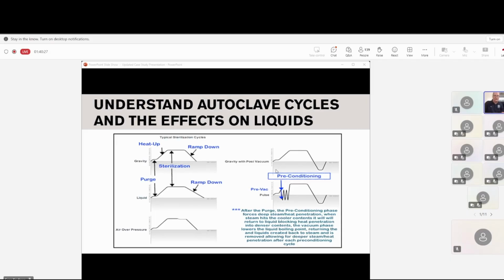When you get to the liquid cycle, which is the same as gravity all the way up to that point, you see the slow ramp down. So at the end of the sterilization, everything just stops. It stops putting steam in, but no valves open. It will sit there for probably 1.5 to 3 minutes, depending on your setting, and then it slowly ramps down. And what it's trying to do is to match the pressure to the temperature. So as the temperature comes down, it can release a little bit of that pressure in order to keep it from boiling. It's really, really tricky to do. If you're going to lose any percentage of it, it's in the ramp down. You don't lose your water, it's the ramp down.